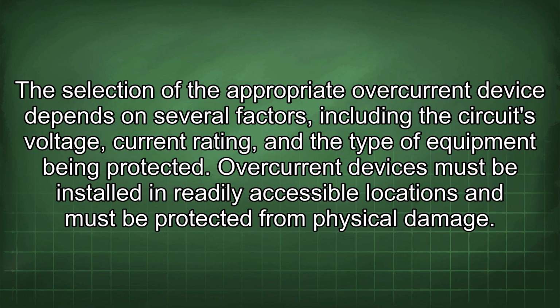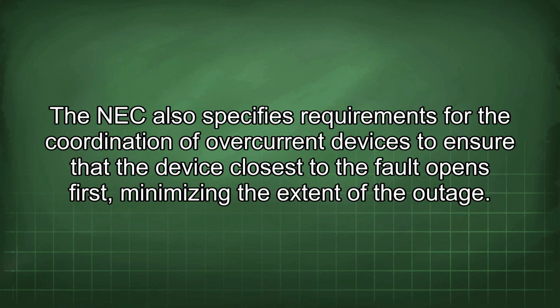The selection of the appropriate overcurrent device depends on several factors, including the circuit's voltage, current rating, and the type of equipment being protected. Overcurrent devices must be installed in readily accessible locations and must be protected from physical damage. The NEC also specifies requirements for the coordination of overcurrent devices to ensure that the device closest to the fault opens first, minimizing the extent of the outage.